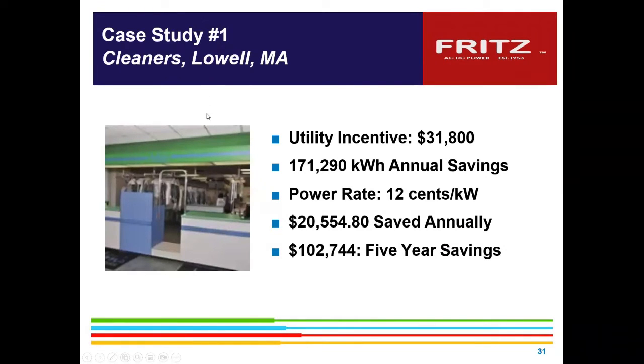This happened to be a case study of a dry cleaner that was utilizing cooling for their systems in the building. They were also using a lot of pumps and fans to run the cleaning facility. We were able to secure a $31,000 energy incentive for the customer. The annual savings was about 171,000 kilowatt hours at a rate of about 12 cents a kilowatt hour at that time. So it made an annual savings for their fairly good sized dry cleaner of about $20,000 annually, just putting these drive controls properly on multiple motors in the plant.